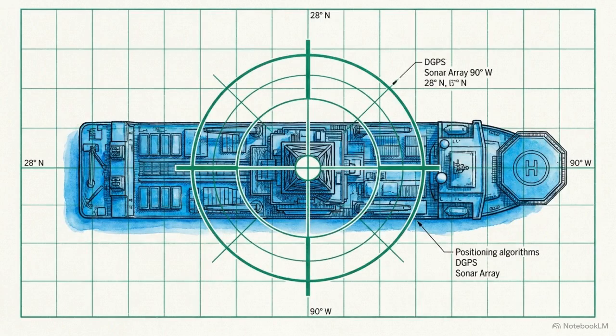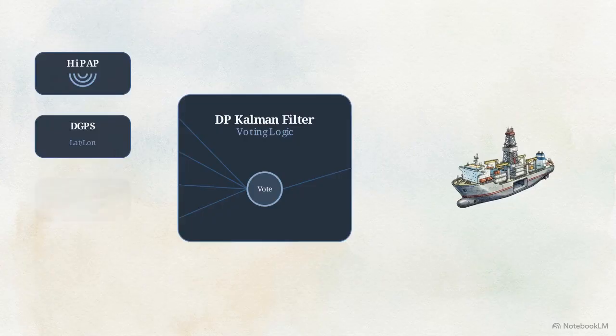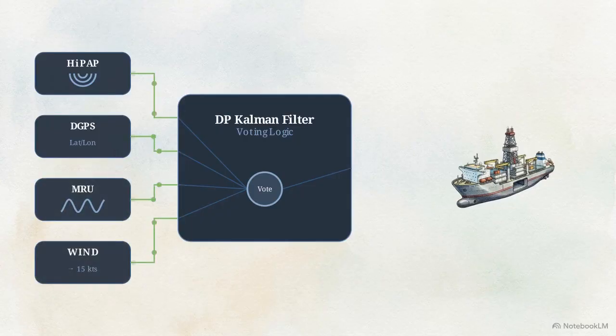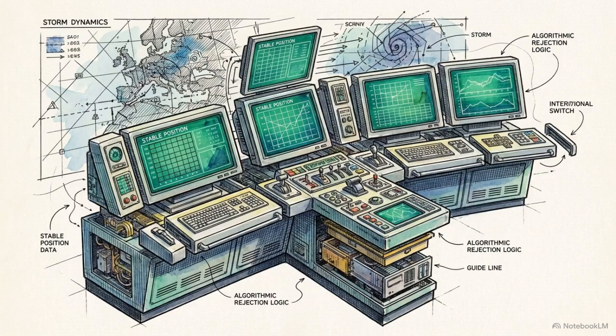This mechanical power is only effective if the control system maintains an absolute understanding of the vessel's geographic coordinates. 4 sensor arrays feed this system: dual HIPAP, differential GPS, motion reference units, and wind sensors. A Kalman filter cross-checks streams in real time. If a sensor suffers signal loss, the system rejects the outlier, calculating thrust on validated data. Dynamic positioning relies on this algorithmic data rejection to maintain station-keeping integrity in changing environments.